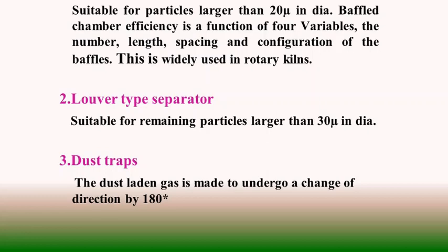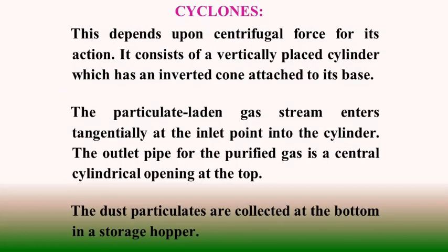Louver type separators are used for larger particles — 30 microns and above. In some places, dust traps are used, which separate particulates from gas by a 180-degree reversal of the flow passage, thereby separating the dust medium from the gas medium.